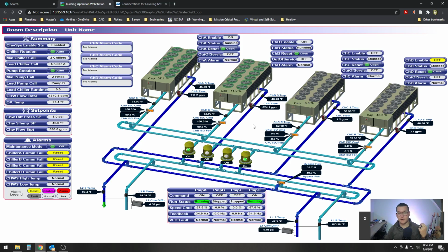And then to maintain minimum flow over the system is where this bypass valve comes in. And as we've already talked about, as this chiller flow increases, this will actually decrease, and then obviously the converse will happen too. And then the last thing is the temperature set point, the supply water set point.